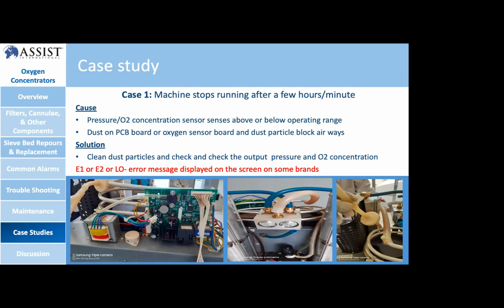As a solution, to fix this problem we clean the dust particles and check the sensor, the oxygen sensor or pressure sensor. Then we use an analyzer to read the pressure outputs and an oxygen concentration analyzer to check the output oxygen concentration. If there is any dust particle in the airways or in the PCB board electronic components, we clean it, and normally we fix this problem in this way.